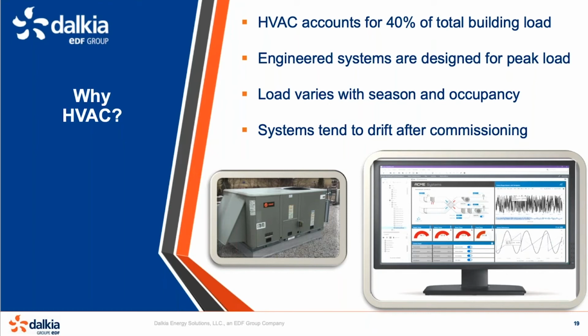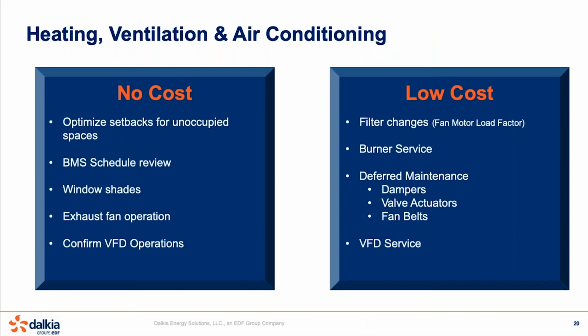But we find that the systems tend to drift. When they're installed, they're set up and commissioned, but temperature sensors drift and things don't operate as intended. So this is a great opportunity for no cost and low cost measures. And in the world of COVID, again, a lot of customers are telling us that everyone's working from home, our spaces aren't occupied. So going through the BMS if they have one, and scheduling that to not be occupied if there's no one there, so we don't need to be conditioning that space. It's always good to review.